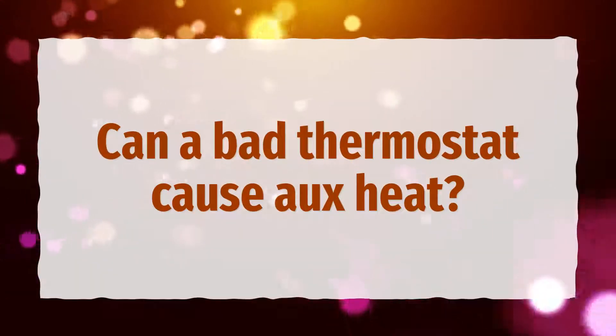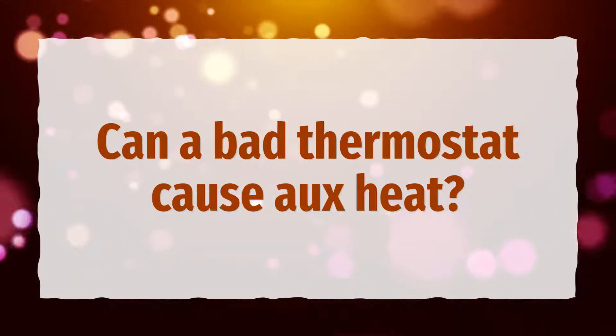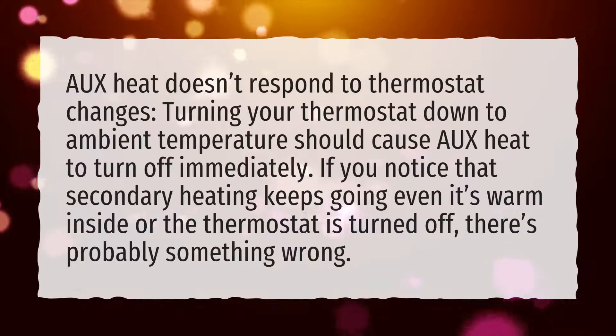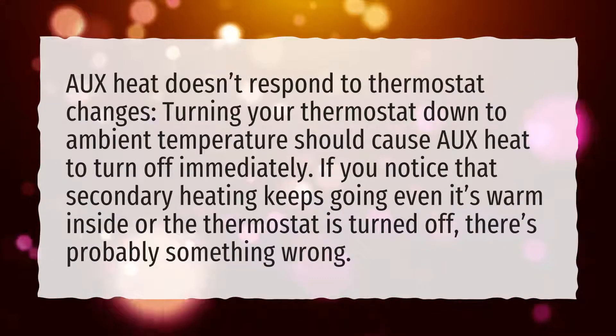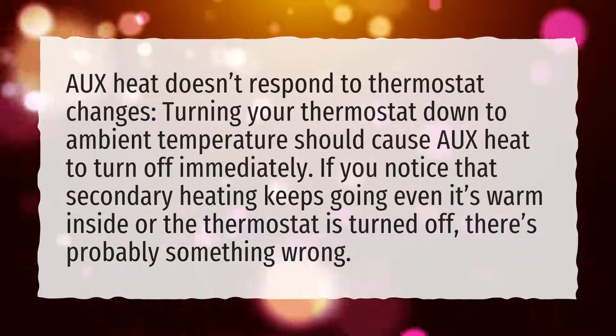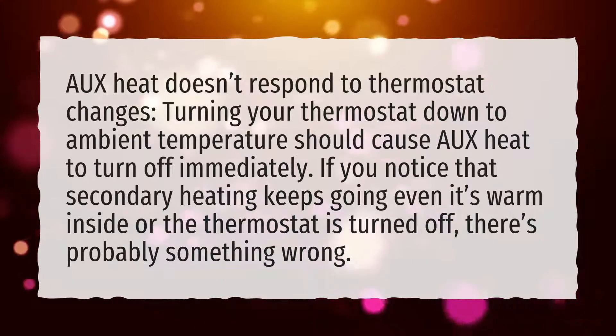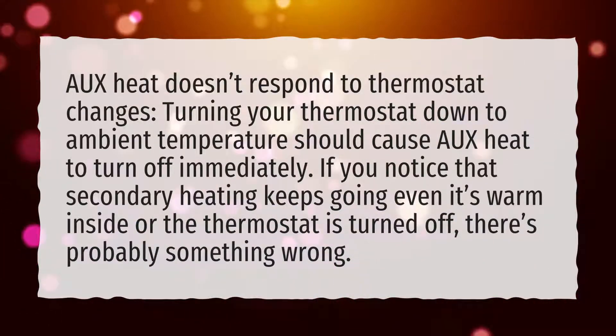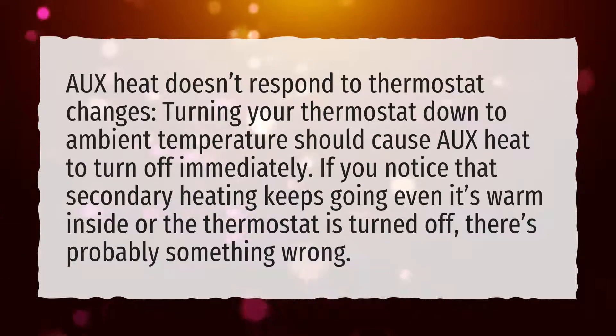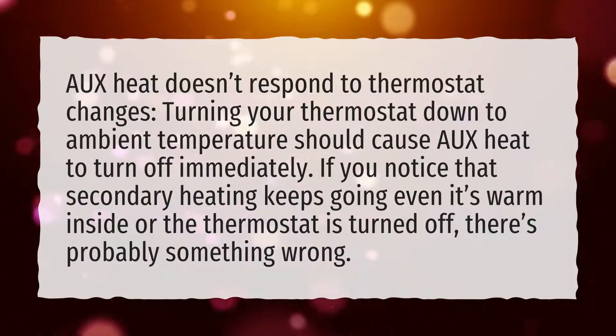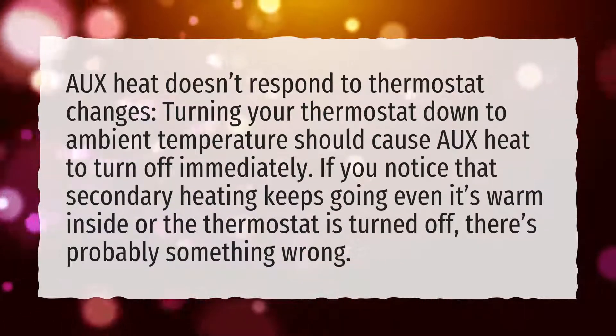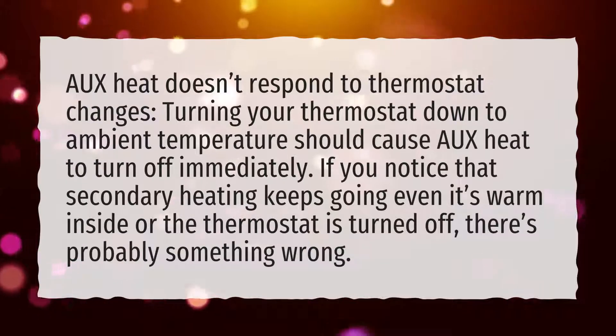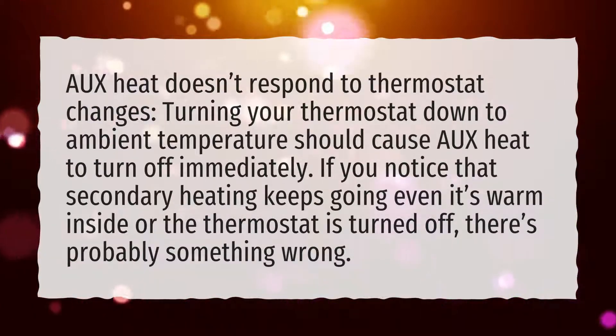Can a bad thermostat cause aux heat issues? Aux heat doesn't respond to thermostat changes. Turning your thermostat down to ambient temperature should cause aux heat to turn off immediately. If you notice that secondary heating keeps going even when it's warm inside or the thermostat is turned off, there's probably something wrong.